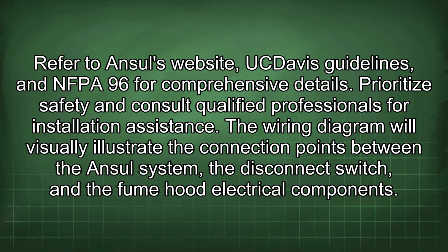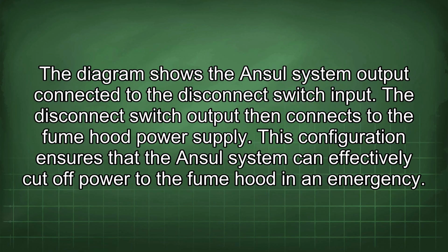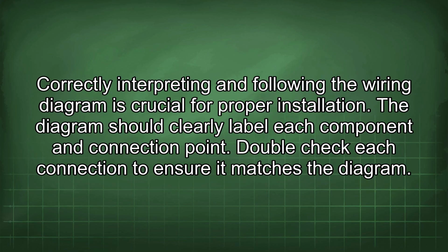The wiring diagram will visually illustrate the connection points between the Ansul system, the disconnect switch, and the fume hood electrical components. The diagram shows the Ansul system output connected to the disconnect switch input. The disconnect switch output then connects to the fume hood power supply. This configuration ensures that the Ansul system can effectively cut off power to the fume hood in an emergency. Correctly interpreting and following the wiring diagram is crucial for proper installation.